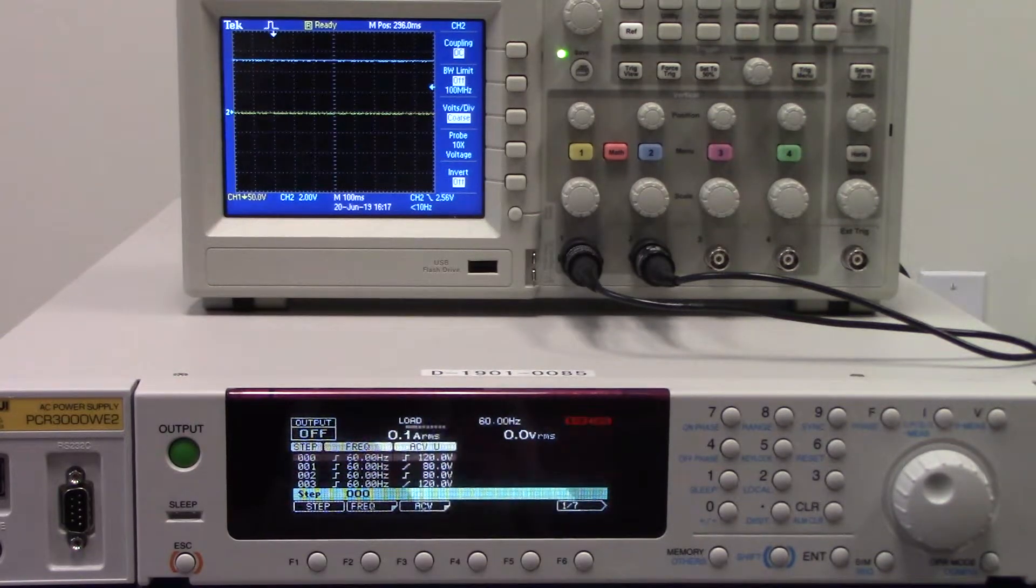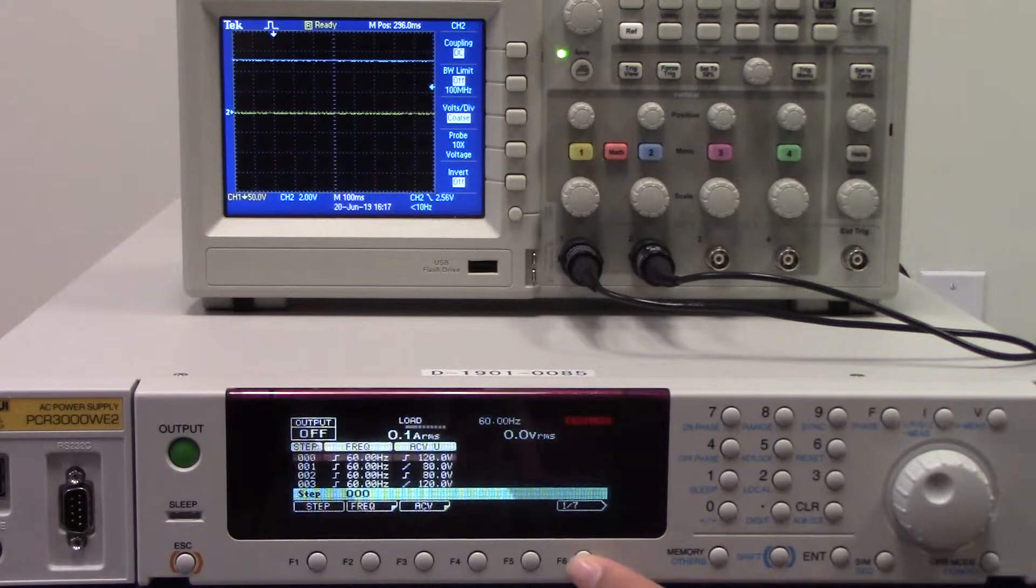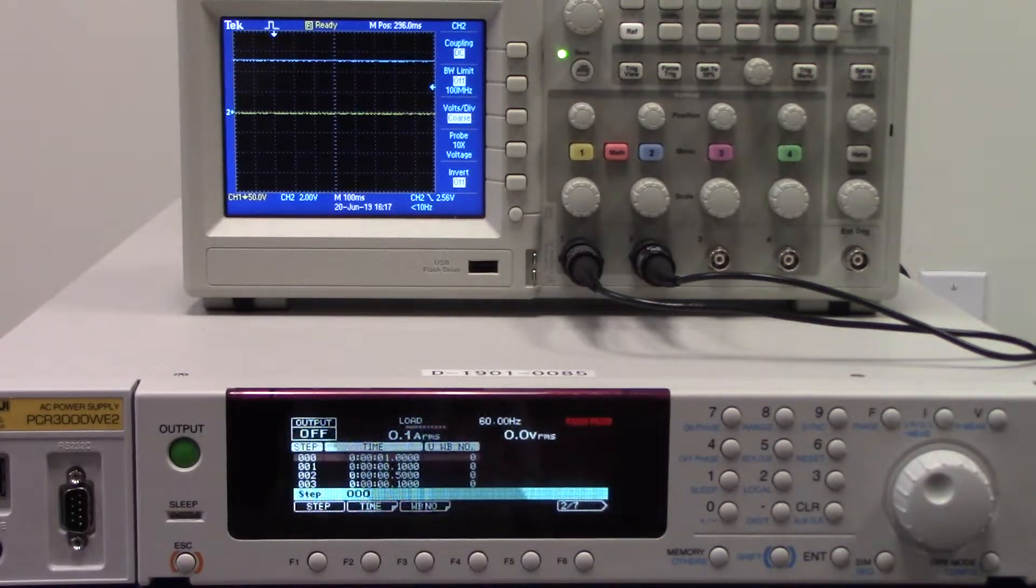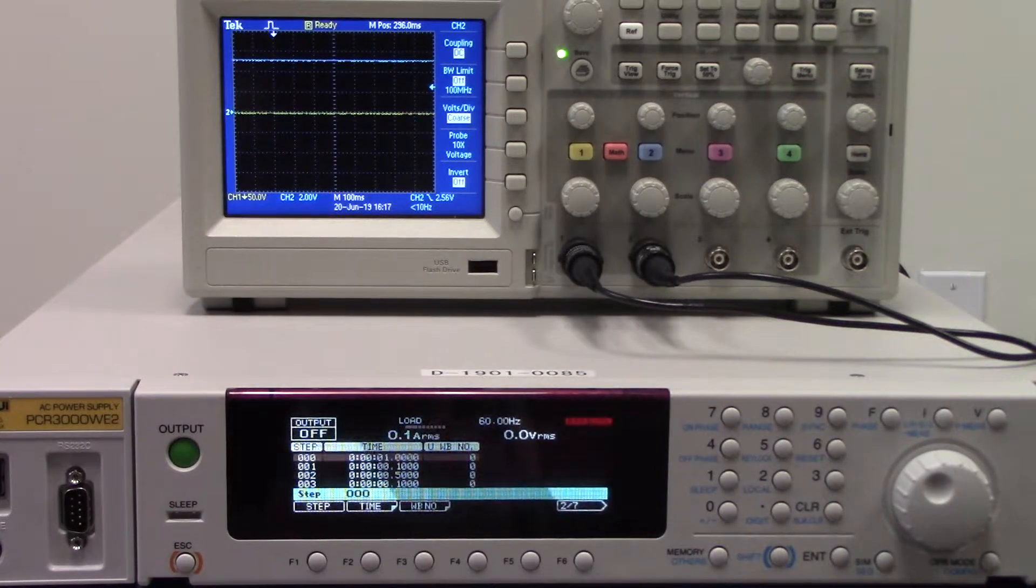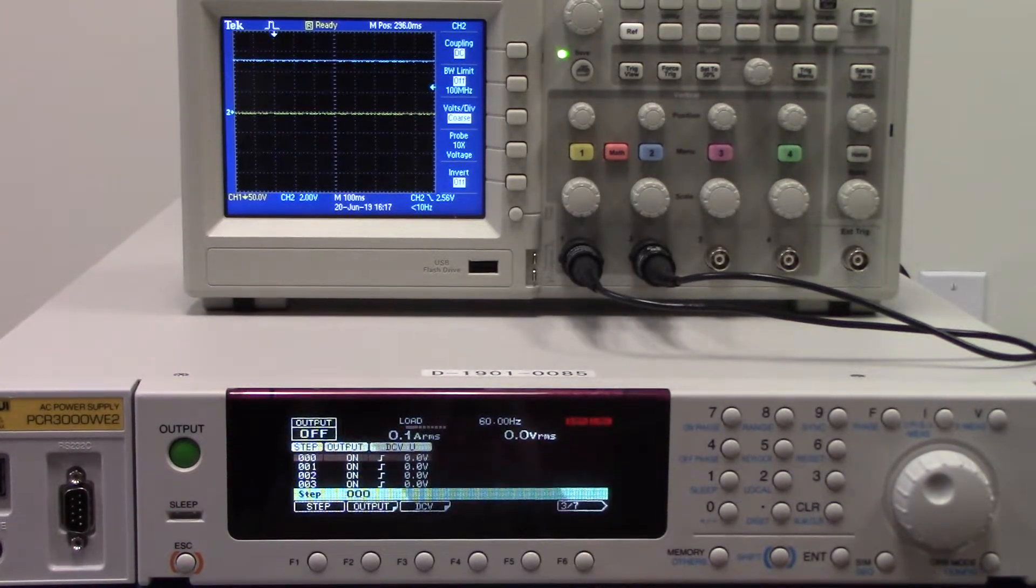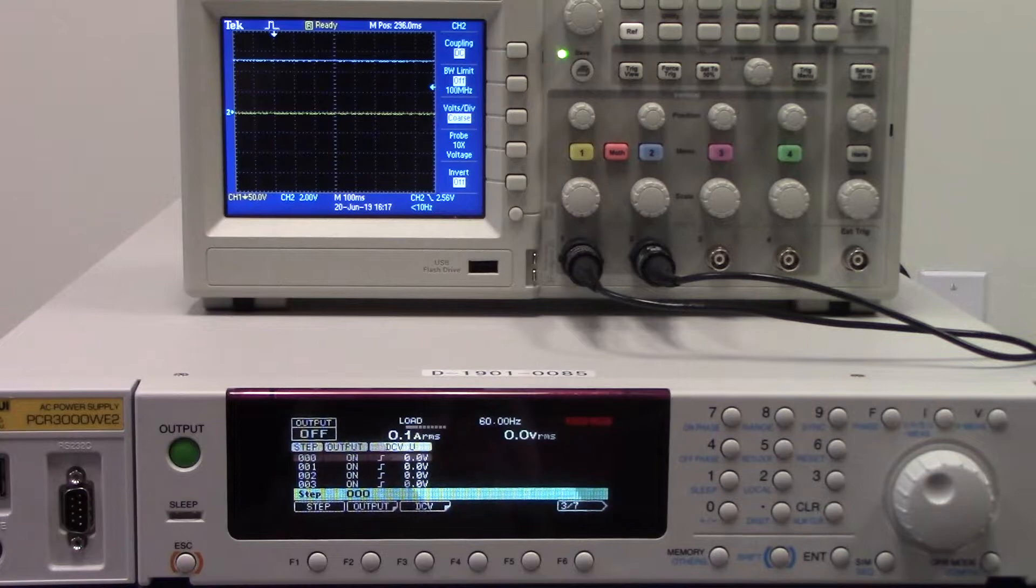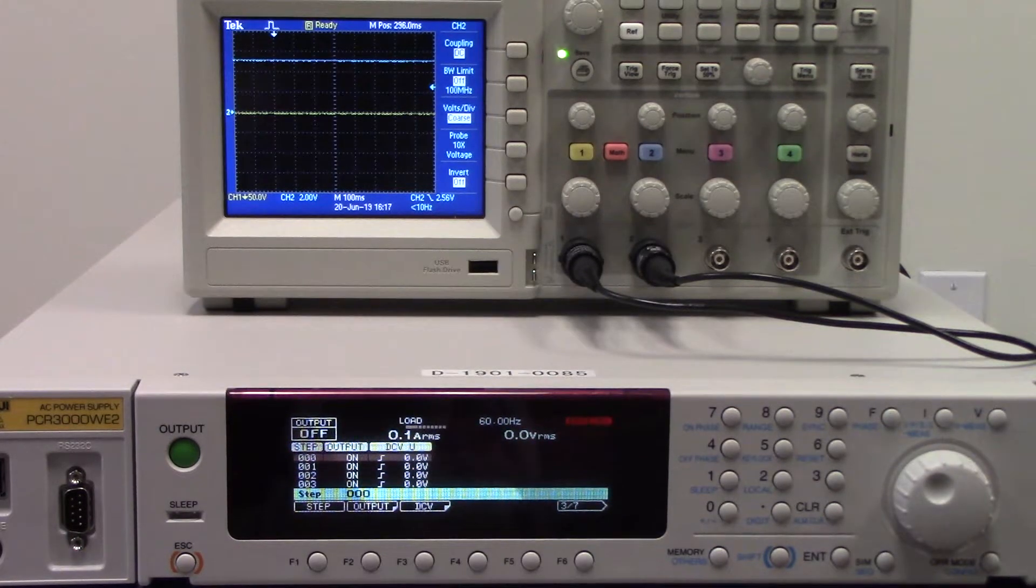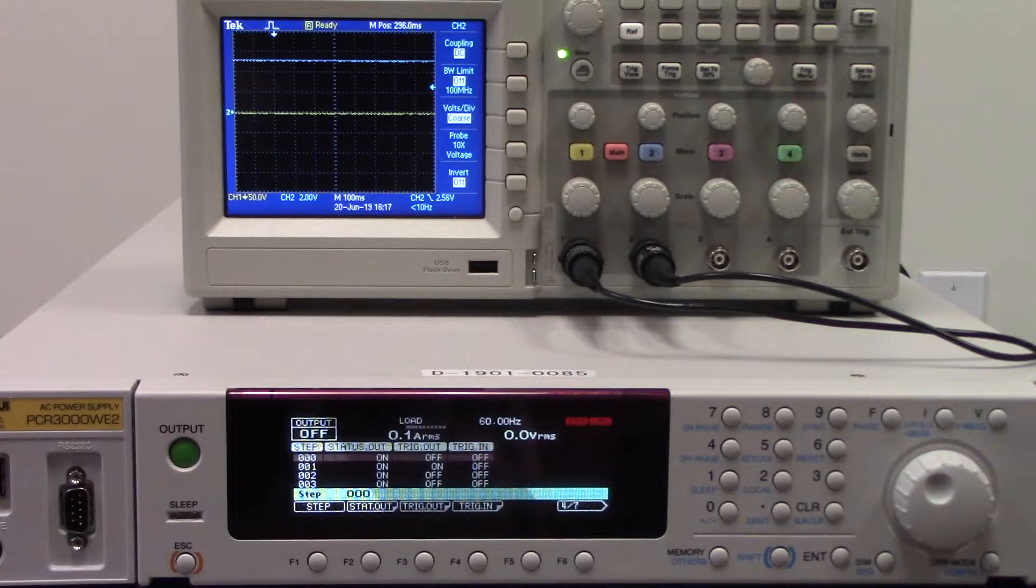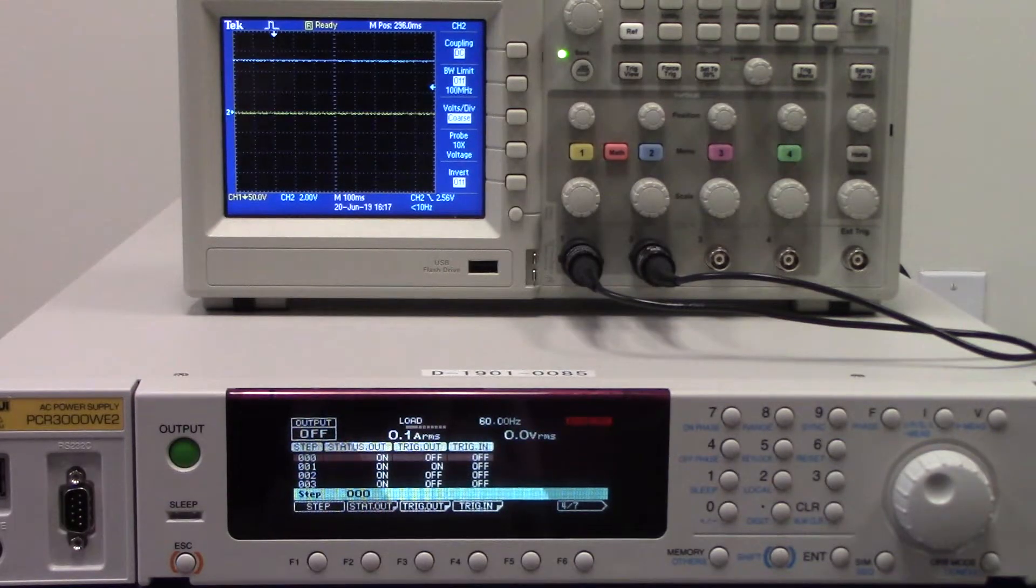You will go to press F6 and it will take you to the next screen. This will show you the time. By pressing F6 it will take you to the next screen showing you the DC voltage. Pressing F6 again will take you to the next screen showing the status output, trigger output, and trigger input.